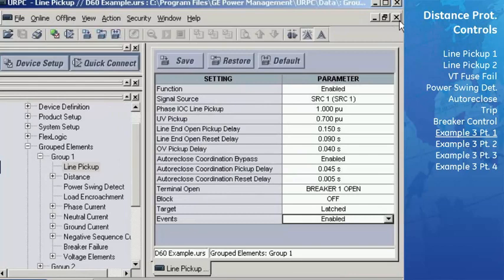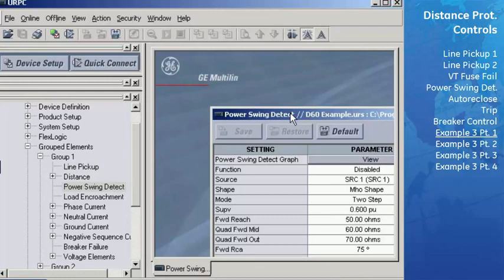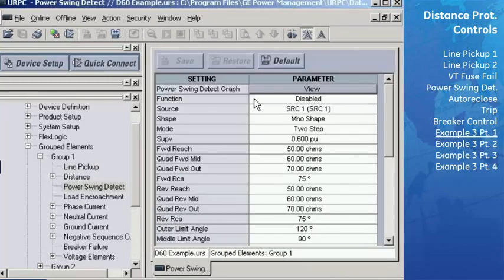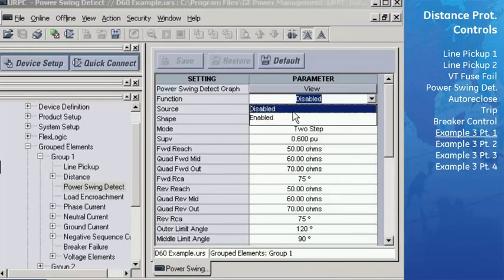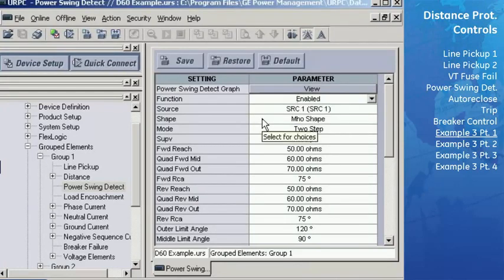Then save these settings to the settings file and close this window. We will now configure the power swing blocking element. Go to Grouped Elements, Group 1, Power Swing Detect. Enable the scheme by setting the function field to Enabled. Keep the signal source setting as Source 1, which is the same as the source used by the distance element.